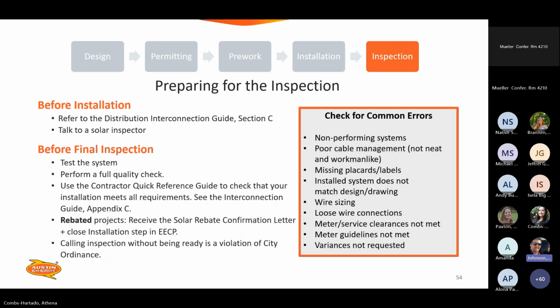Other things that can obstruct clearance are plants. I've been to one where they had three very large mountain laurels a foot in front of the service. I couldn't even get in there to open up the panel, and I had to put on there that I could not do the inspection because of trees in front of the service, and I had to ask that those be removed. How they were to be removed was up to the homeowner, but they had to be removed. Meter guidelines not met, whether it be for wiring, the meter base being the incorrect type, and then variance is not requested. Building it and asking for forgiveness later, not working very well right now, not recommended.